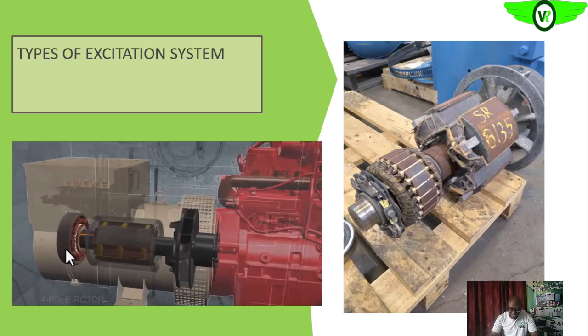So this type of excitation system we've been discussing is called the brushless exciter. Brushless in the sense that there are no brushes carrying power from one unit to another. The field is on the stationary part, the armature that produces is on the rotor, then the diode assembly, or diode plate, is also coupled to the rotor, and the output is sent to the main field. So there are no brushes. This is the brushless excitation system, or we can say the rotating exciter.